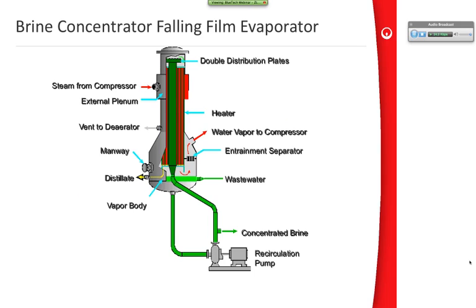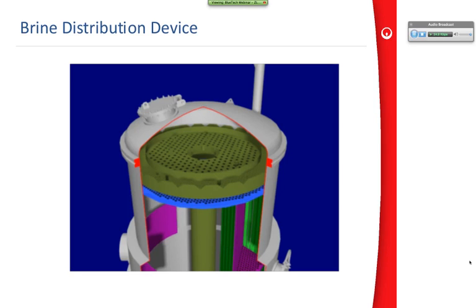The heart of the brine concentrator is the falling film evaporator. Again, it's a tube bundle with a distribution device located at the top. There's a recirculation line and a recirculation pump, which bring the brine to the top of the heat exchanger, where it falls down the tubes. Evaporation occurs within the tubes because water vapor is condensing on the outside of the tubes. The distillate is collected and pumped out of the system. The water vapor goes to the compressor. Again, that's a typical falling film.